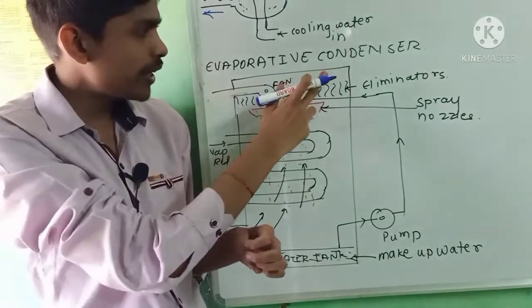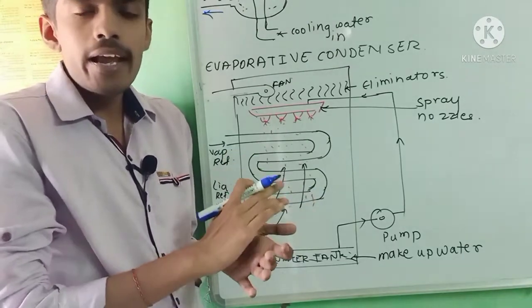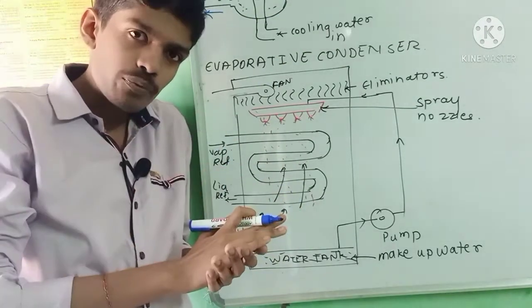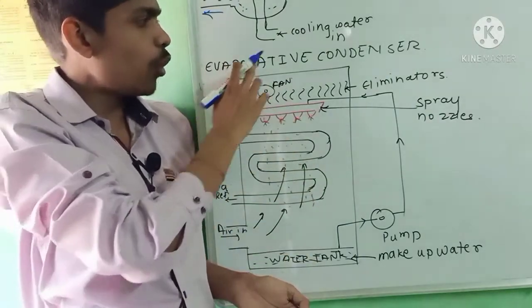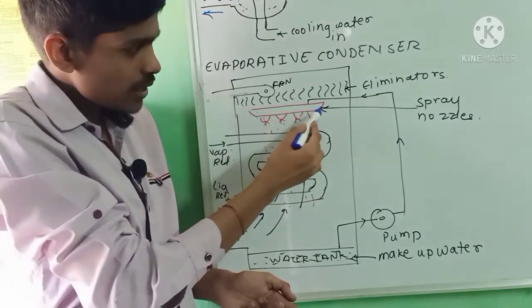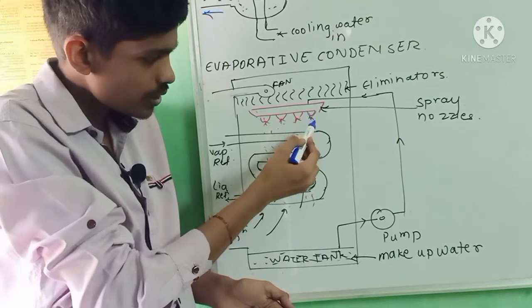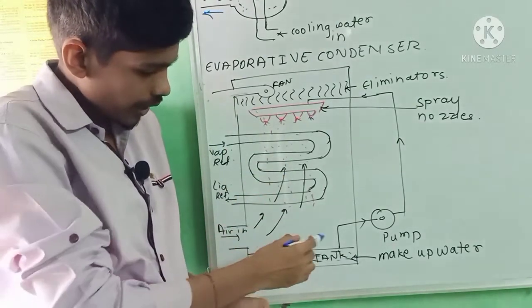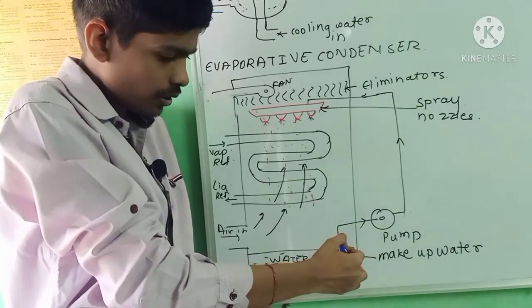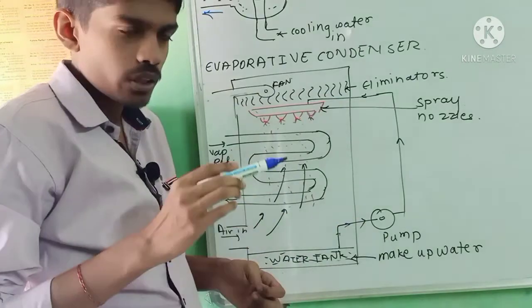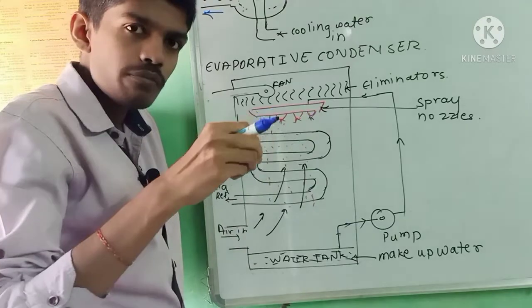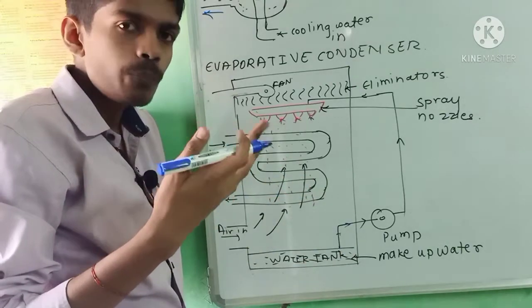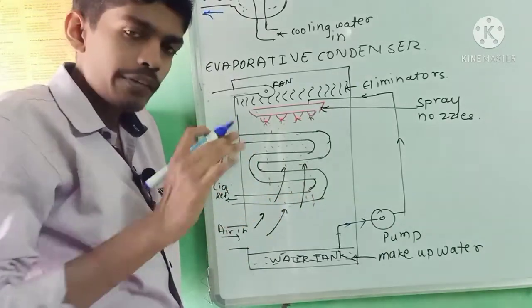Next is the evaporative condenser. In this type, both air and water can be used as the cooling medium. It includes a spray header with spray nozzles through which cooling water is sprayed, and drift eliminators. A fan is present, and vapor refrigerant enters from the top. A pump takes water from the sump and delivers it to the spray nozzles. The spray nozzles spray water over the refrigerant tubes, heat transfer takes place, and vapor refrigerant is converted into liquid refrigerant, which is sent to the receiver.